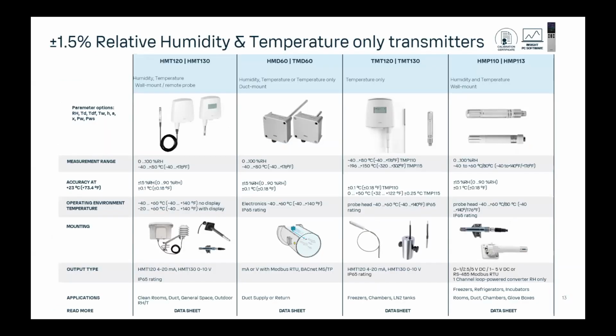So moving along in our products, this is our line of plus or minus 1.5% humidity. So not as accurate as those HMP X probes, but still on the high end side. These still come with traceable calibration certificates to ISO 9001 compliance. Just a bit of a stripped down design of that humicap sensor that doesn't have the same chemical purge option that we would have here.